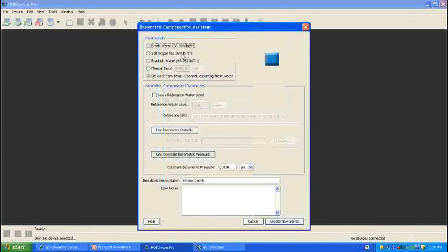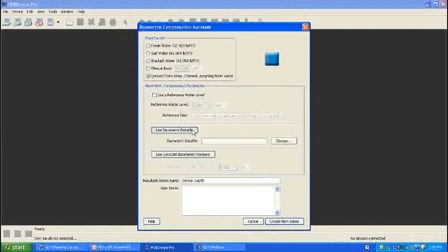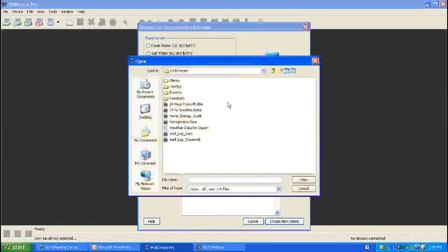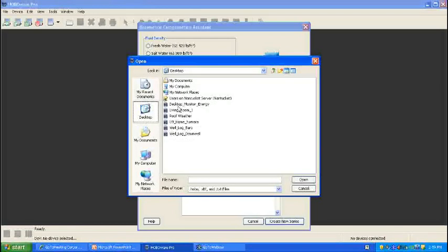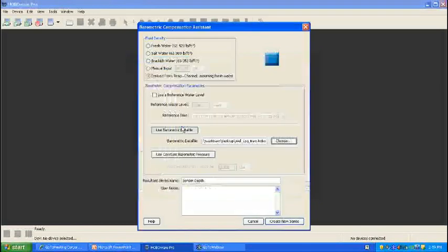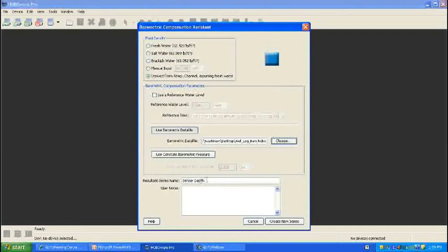Now first you must select the density, and since we did log temperature at the same time as pressure, we're going to go ahead and use that as your most accurate choice, and we were in fresh water. For the compensation parameters, we were also logging barometric pressure at the same time as the water level logger, so we will select that data file. And we have all our files. Okay. Here's our barometric pressure file. And we'll go ahead and leave the default name of sensor depth.